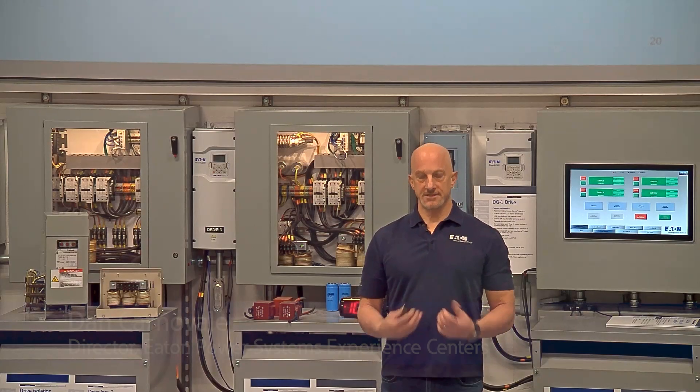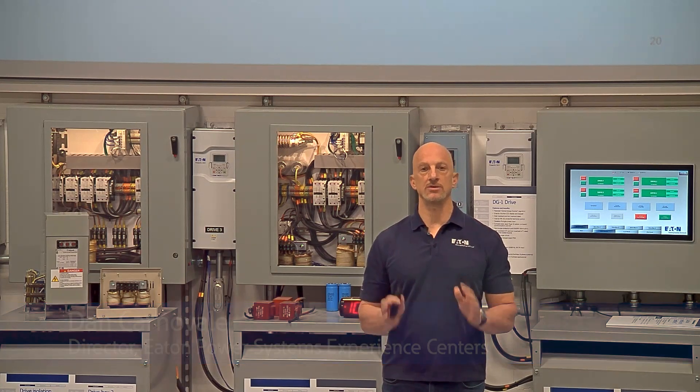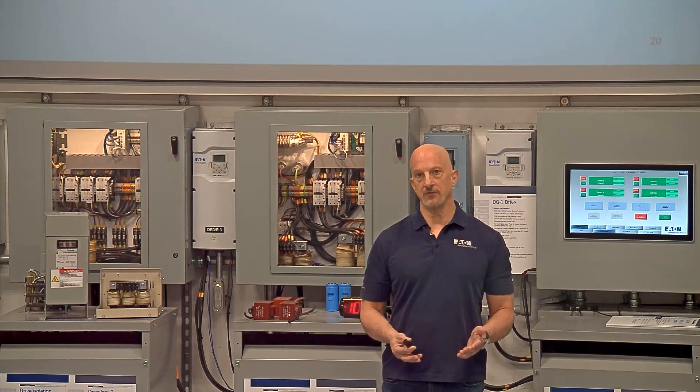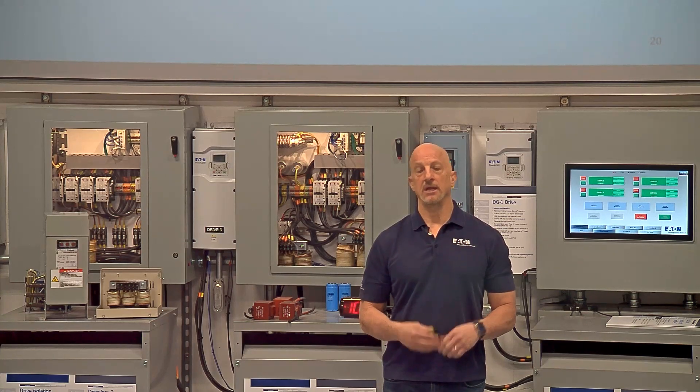A lot of times you might have existing power factor correction capacitors and you find that you have a lot of harmonics or you created a resonant condition. So can you change an existing power factor correction capacitor into a harmonic filter?